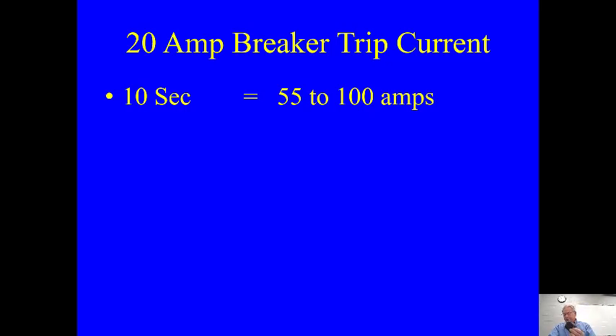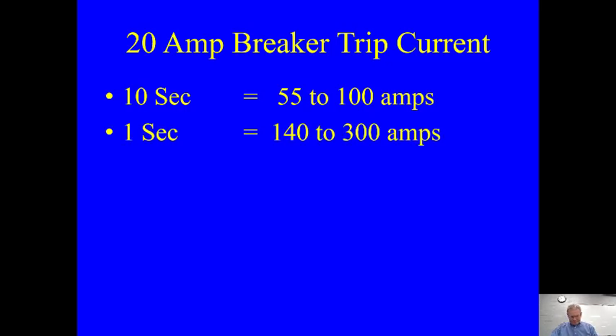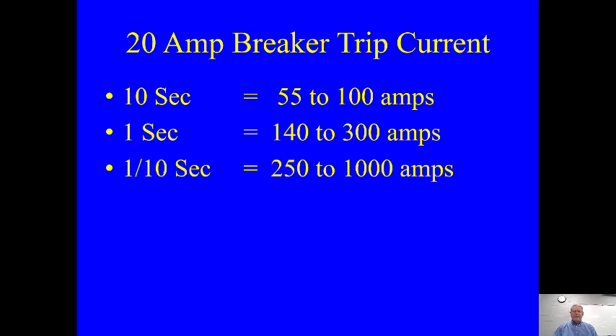So it looks a little different to this, a little bigger, but it's still a 20 amp breaker. If you reset it and it takes 10 seconds to trip, GE says that it's going to trip between 55 and 100 amps on a 20 amp circuit. Now I'm holding a 15 amp breaker here, but a 20 amp breaker looks the same. If it trips in 1 second, you have 140 to 300 amps going through that breaker. And if it takes a tenth of a second, you have between 250 and 1,000 amps going through a 20 amp breaker.